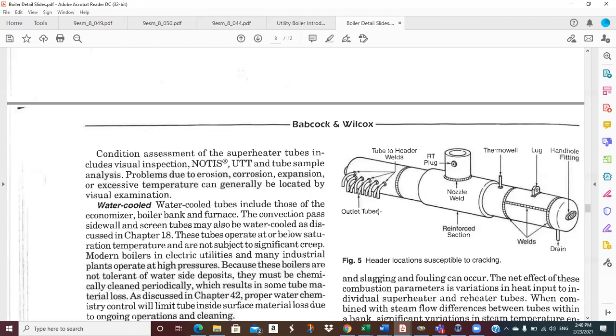Now, like I said, at the top of the boiler, all that steam and water would be dumping in from those tubes into this thing, and then you would have one pipe taking all of that, say, to the drum. So you've got multiple headers around these large boilers. And every time you cycle these things up and down in temperature, you induce stresses in them. A hole is a stress concentrator by itself. You put 250 holes in this thing and heat it up and down enough times, guess what? You get cracks. It's going to happen.